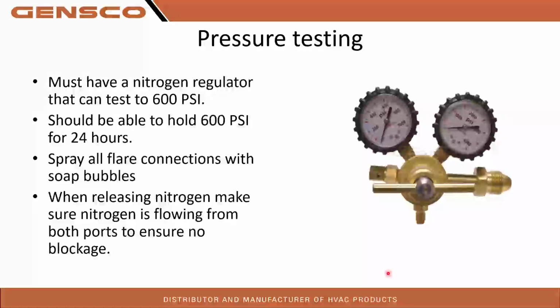Pressure testing. So for those of you guys that haven't done it yet, you're going to need to make sure that you have a pressure regulator on your nitrogen tank that can go up to 600 PSI. So that is going to be a code requirement for the 454 product. So again, all that stuff is going to have to be pressure tested up to 600. So make sure you guys are updating your tools and getting your gear ready for that if you haven't already.